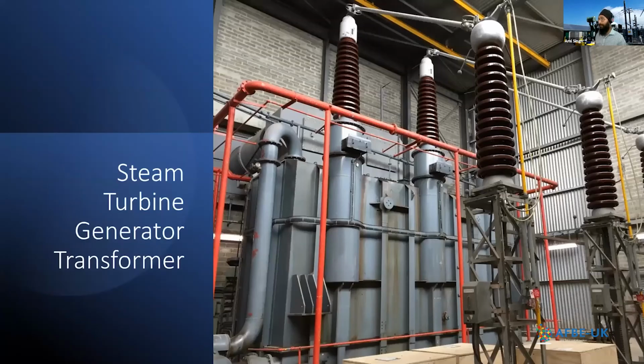This is a transformer photograph from a steam turbine, one of the larger ones in the country, rated at 776 MVA. This is not an air-cooled transformer; instead it relies on oil-water heat exchangers, hence you cannot see a conservator or radiators in this photograph. Power comes out through the bushings and bus bar connections via 275 kV, supplying power to the national grid.